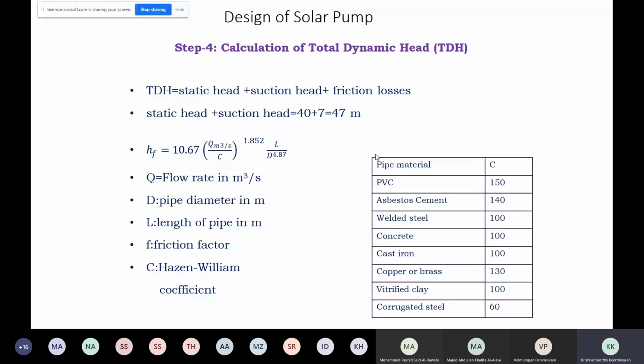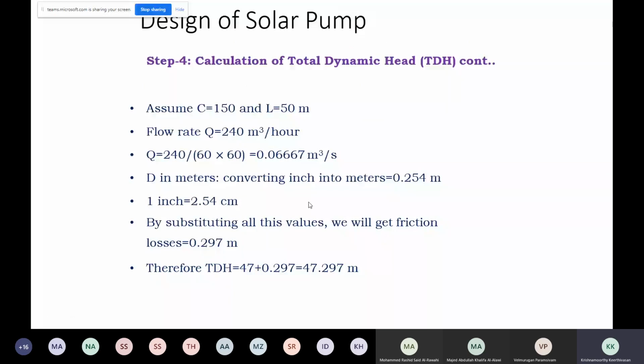Frictional losses we have calculated in the next slide, I think. You see here, 0.297. For this we have given: what is C, what is the length in meters, what is the flow rate, Q, flow rate divided by time, per hour, how many minutes, how many seconds. 3600 will give you 0.0667 meter cube per second. Converting inches into meters: 1 inch equals 2.54 centimeters. By substituting these values, we found the frictional losses to be 0.297. Already 47 plus this frictional loss will be 47.297.